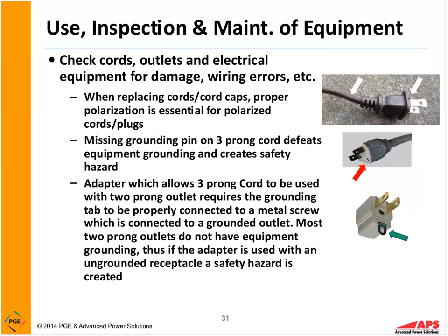Now, if someone flips the hot and the neutral, the black and the white wire, which you can't see here, but if you were able to picture it that way, the wider blade should be the white wire. In other words, if I put a new cord cap on a toaster and flip it the wrong way, and I have the toaster plugged into a wall, let's say it's not a GFCI protected receptacle, which is going to help protect against shock, but if someone reached down in that toaster with a fork, which they shouldn't do, of course, and touched one of those elements, even with the toaster off, if the polarity of the cord is reversed, they would be exposed to an energized conductor. If the polarity is correct, it's less likely that they would be exposed to that.